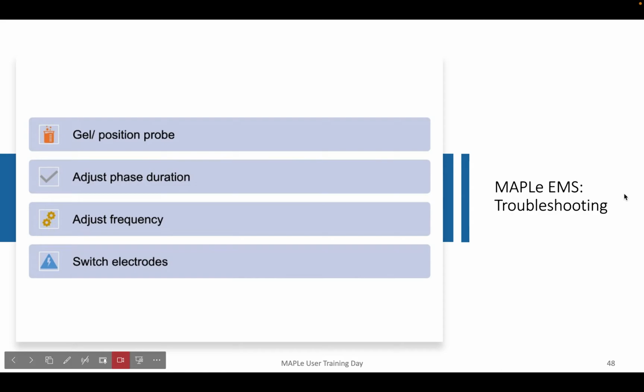So in terms of electrical stimulation troubleshooting, we need to think about, have you got enough gel on the probe? Is the probe in the correct position? Do you need to adjust the phase duration, taking the phase duration down if it's too uncomfortable, or increasing the phase duration if the patient is unable to feel anything? Do you need to adjust the frequency to target the muscles specific to the problem? Or do you need to switch the electrode choice from ring to side, for example, to access the sensations necessary within that area?